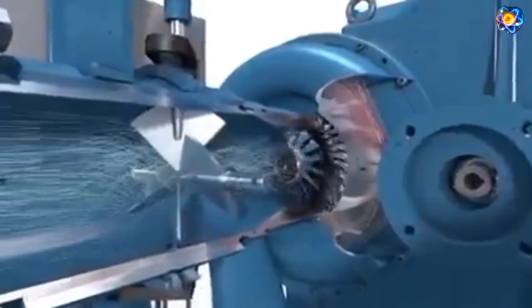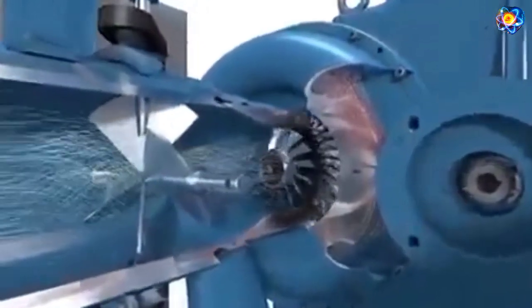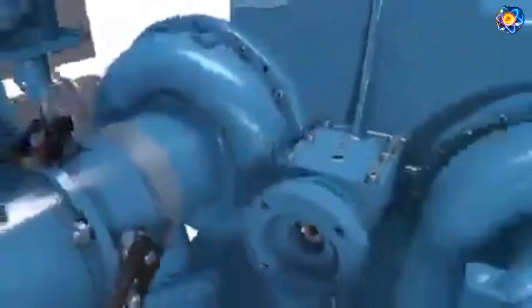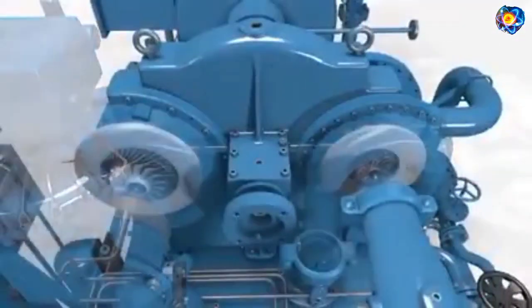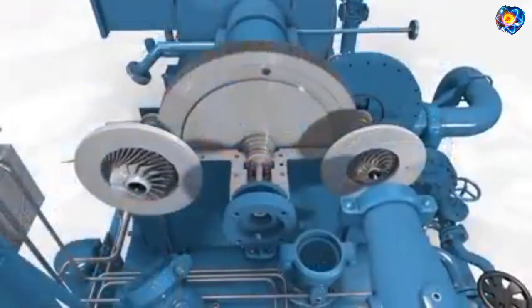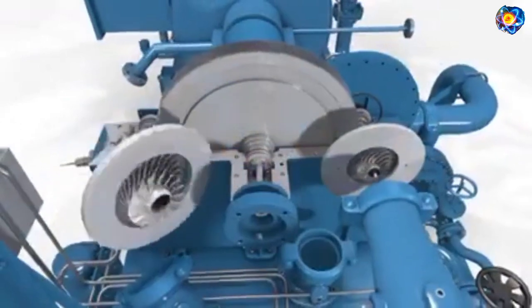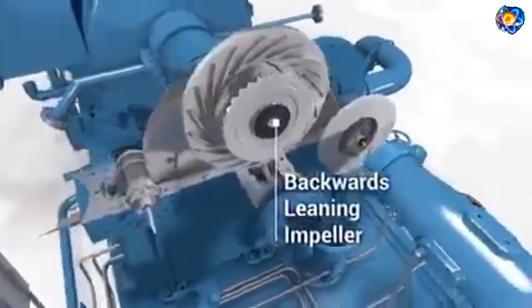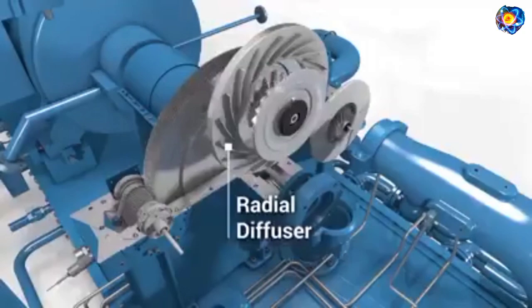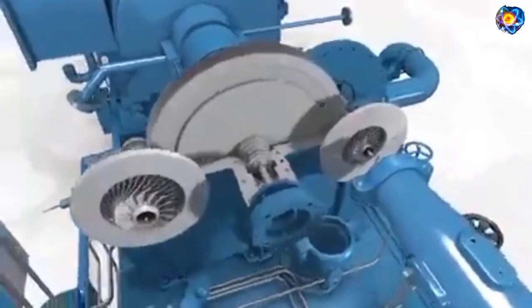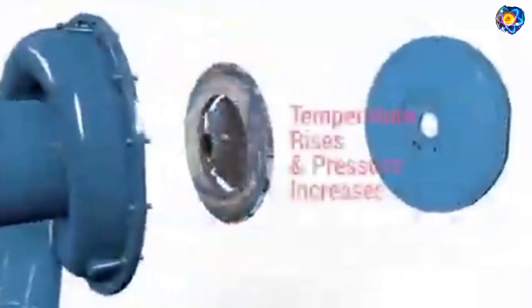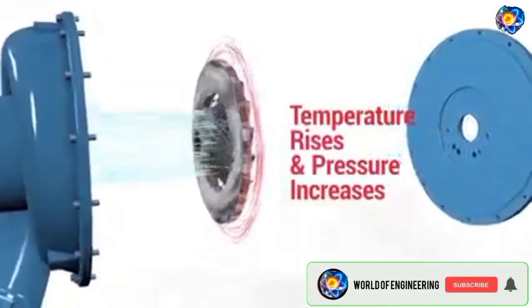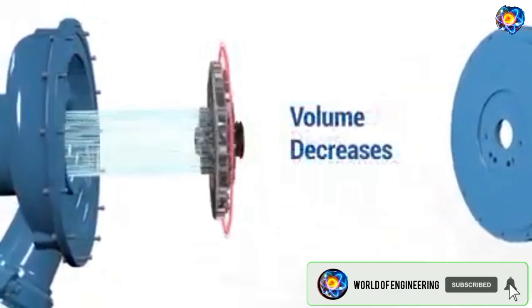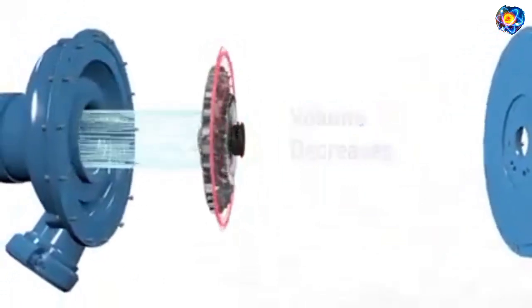From there, the accelerated air or gas stream flows from the first stage impeller to a radial diffuser, which converts the air's high velocity into static pressure before the heated air enters the scroll casing. To ensure perfect aerodynamics, FS Elliott will custom design both the backward-leaning impeller and radial diffuser for your specific application. With each stage of compression, the air or gas temperature rises, pressure increases, and volume decreases.